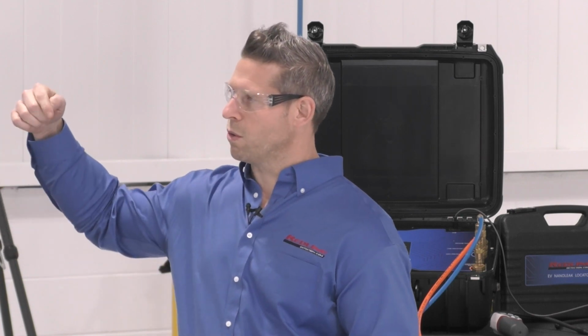In a vacuum test, it's a little bit more like the real world, in the aspect that you're looking for vapor getting inside of the battery. You're creating a flow path in towards the center of the battery rather than out of the battery. So you could argue that's a great test to determine if you're getting an inflow risk into your battery - that's probably the best test.